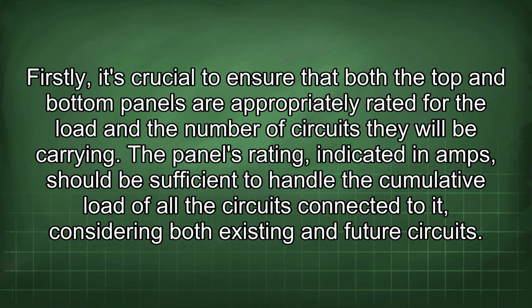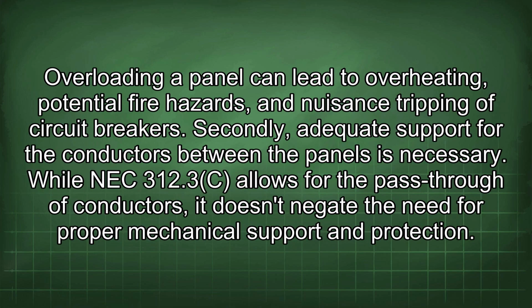Firstly, it's crucial to ensure that both the top and bottom panels are appropriately rated for the load and the number of circuits they will be carrying. The panel's rating, indicated in amps, should be sufficient to handle the cumulative load of all the circuits connected to it, considering both existing and future circuits. Overloading a panel can lead to overheating, potential fire hazards, and nuisance tripping of circuit breakers.